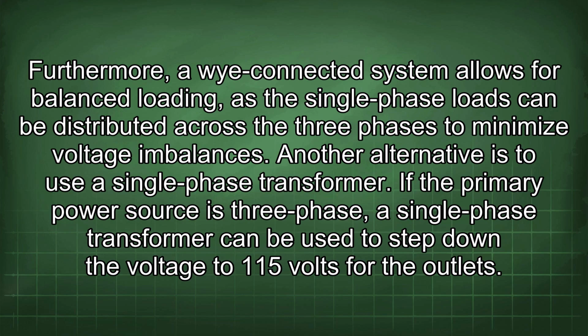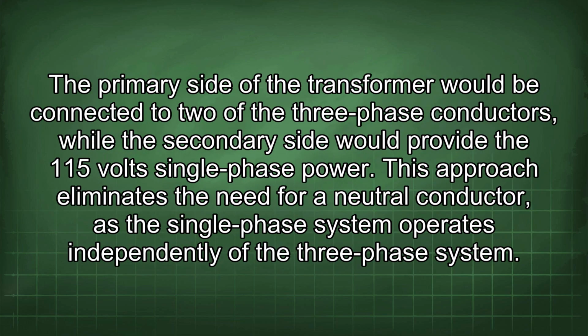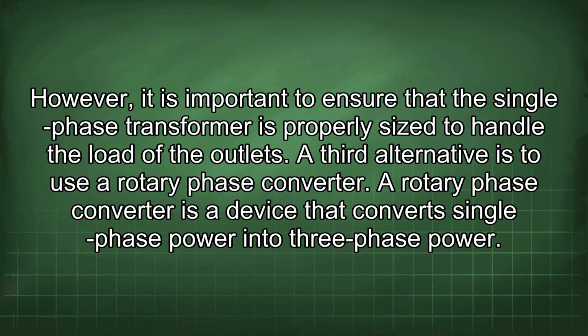Another alternative is to use a single-phase transformer. If the primary power source is three-phase, a single-phase transformer can be used to step down the voltage to 115 volts for the outlets. The primary side of the transformer would be connected to two of the three-phase conductors, while the secondary side would provide the 115 volt single-phase power. This approach eliminates the need for a neutral conductor, as the single-phase system operates independently of the three-phase system. However, it is important to ensure that the single-phase transformer is properly sized to handle the load of the outlets.